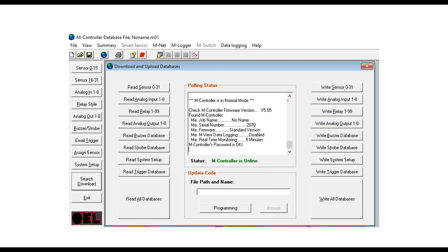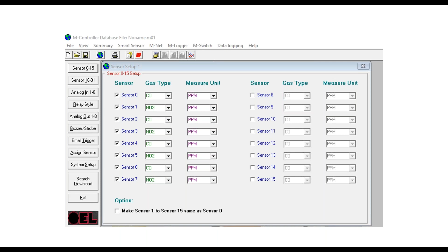So when you first open it up, this is what you're going to see. On the left-hand side is where we're going to do all our programming, the sensors, the relay styles. In this example, we have, let's call it, 4 Q6 CO/NO2. We have 4 CO, 4 NO2. When we address the sensors, we always start at 0. And with the Q6, the remote is automatically a +1. So all our CO are going to be even, all our NO2 are going to be odd. It's going to be really easy to remember.